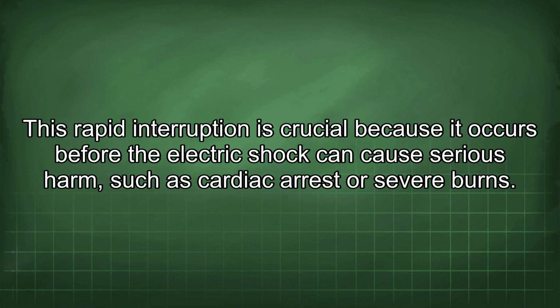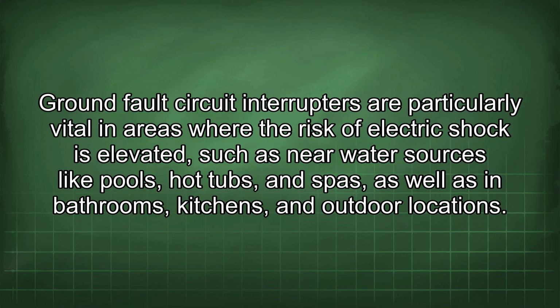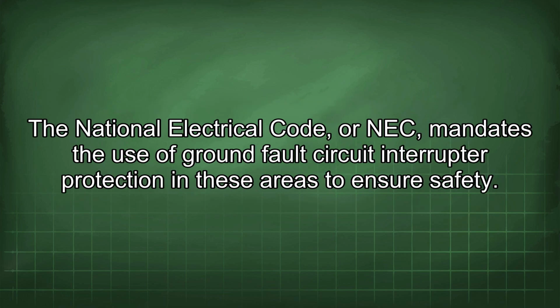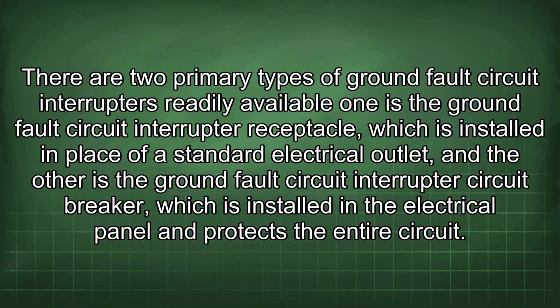This rapid interruption is crucial because it occurs before the electric shock can cause serious harm, such as cardiac arrest or severe burns. Ground fault circuit interrupters are particularly vital in areas where the risk of electric shock is elevated, such as near water sources like pools, hot tubs, and spas, as well as in bathrooms, kitchens, and outdoor locations. The National Electrical Code, or NEC, mandates the use of ground fault circuit interrupter protection in these areas to ensure safety. There are two primary types of ground fault circuit interrupters readily available.